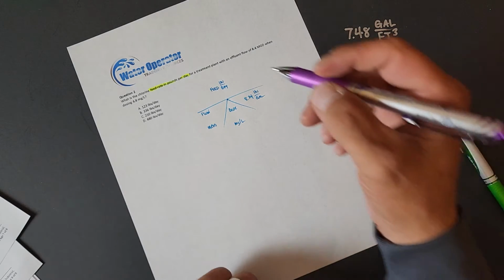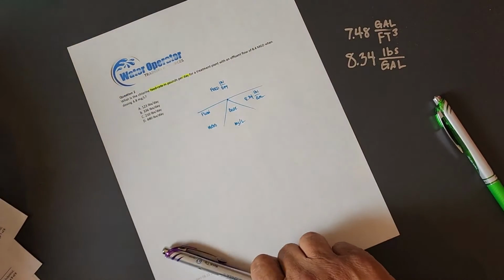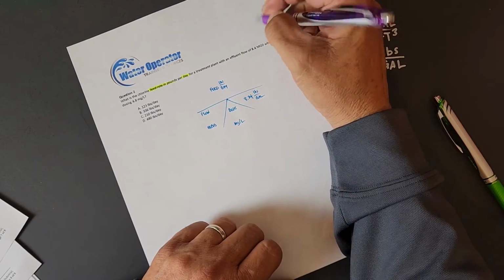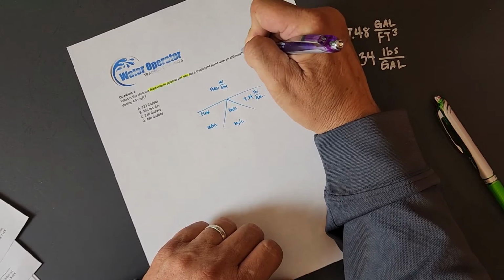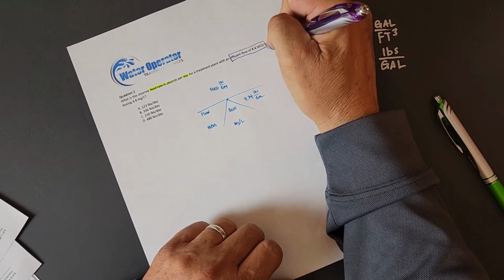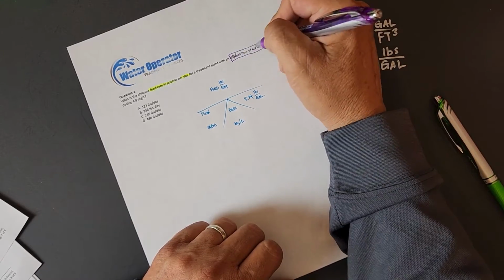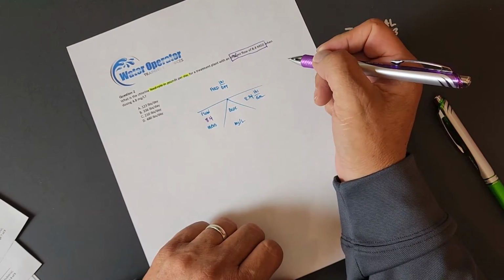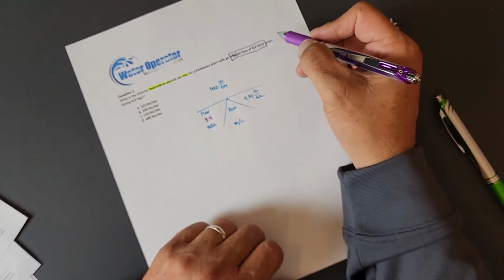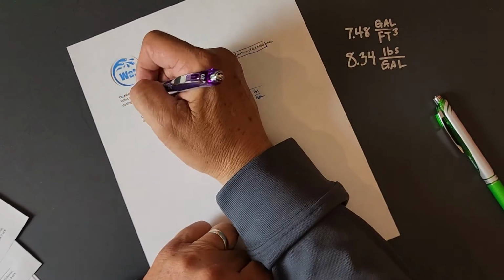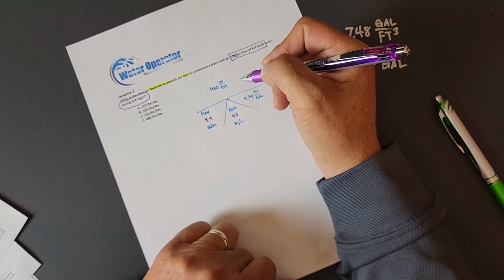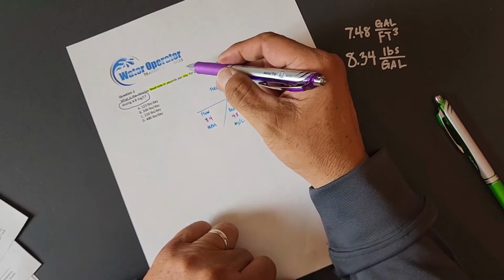We have flow, with an effluent flow of 8.4 million gallons per day. I really didn't need effluent. I just need flow of 8.4 mgd. The dose is 4.8 milligrams per liter. What is the chlorine feed rate in pounds per day?